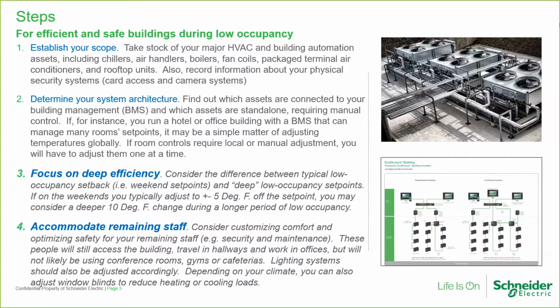A couple things we're hearing quite often: more focus on deep efficiency. Everybody knows about normal setbacks - at nighttime when your building goes into setback, or on weekends for an office building, for example. In these times, you can go into a much deeper setback, because you don't have to recover as quickly in the morning to get the building cool for people coming in. So you may set back to 82 or 85 degrees instead of 80, for example, in southern climates - though we have a lot of northern clients where it's the opposite.